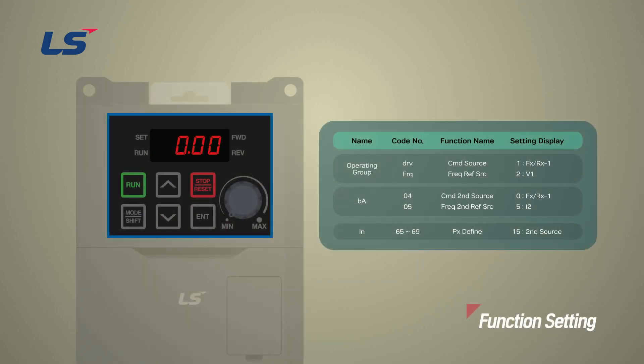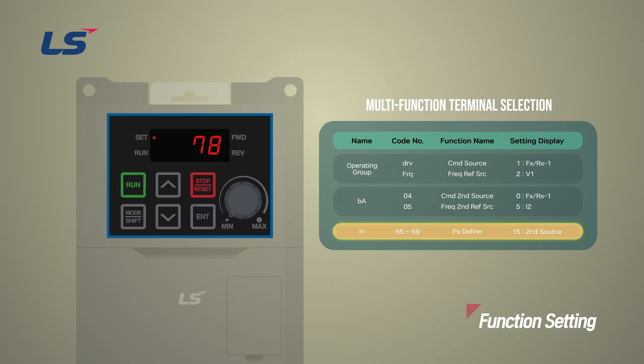To use the second operation mode, select one of the multi-function terminals and select it as the second source. Let's program the second operation using the multi-function terminal. Move to the IN group and select one of number 65 to number 69 and set it to number 15 second operation function.